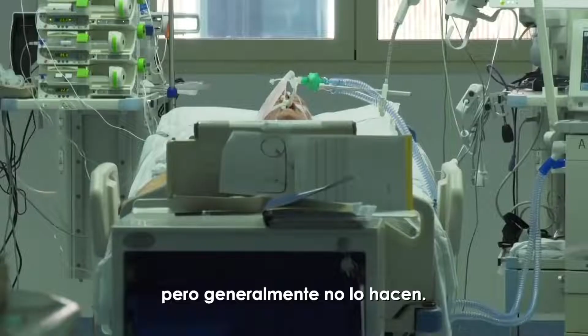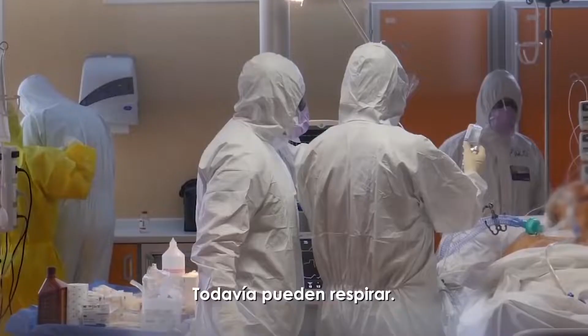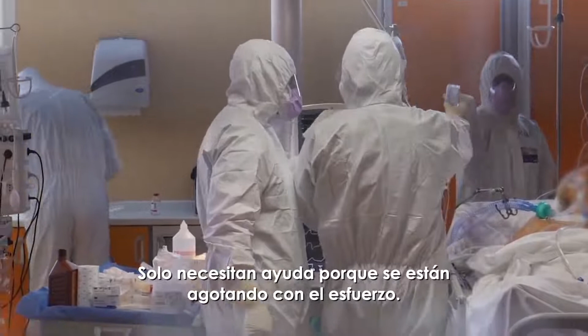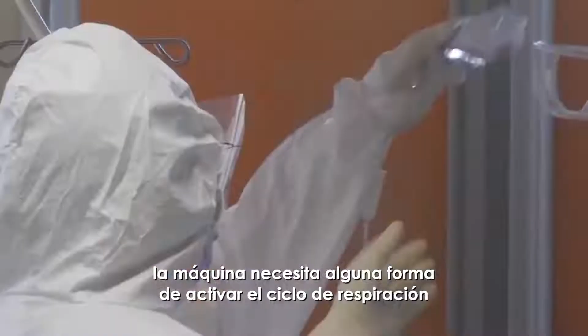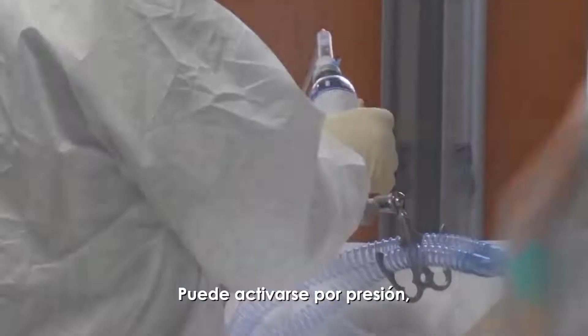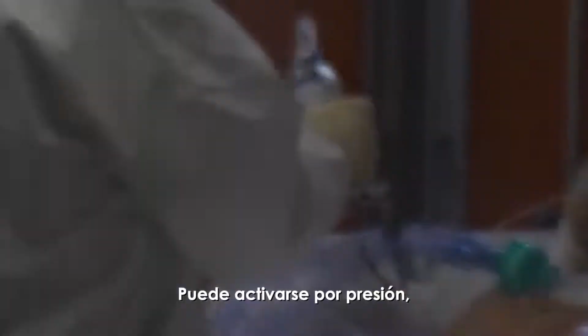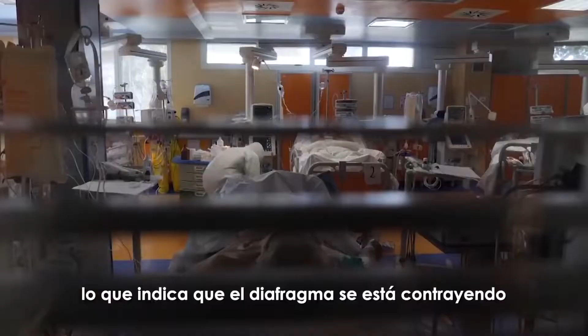High-performance ventilators can work like this, but they typically don't. Their breath sequences are normally triggered by the patient. They are still able to breathe. They just need help because they are exhausting themselves with the effort. In order to do this, the machine needs some way of triggering the breath cycle and ending it too, based on observations of the patient. This can be done in a number of ways. It can be pressure triggered, where a sensor detects a drop in airway pressure, indicating the thoracic cavity is expanding. It can be flow triggered, where a sensor detects airflow into the lungs, or it can be triggered by a sensor detecting electrical activity of the diaphragm, indicating that the diaphragm is contracting to expand the thoracic cavity.